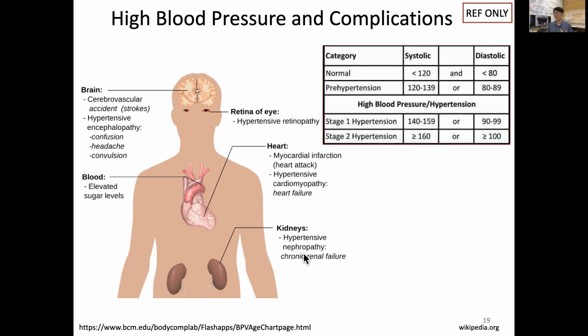And because of that, let's talk about measurement of blood pressure. Traditionally, this is called the auscultatory method, and auscultation means listening to sound within the body. Remember, with a pressure cuff you release the pressure, shown as the gray line over time, and the red is your arterial blood pressure. When cuff pressure is higher, it squeezes the artery completely, so you don't hear any sound. But once it's in between, the flow starts to move, and the pulse generates turbulence, which causes a sound. That's called the Korotkoff sound.